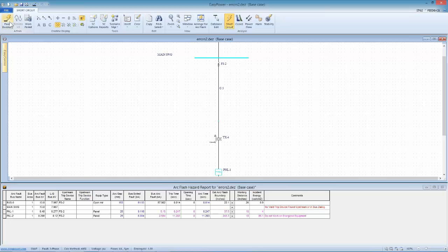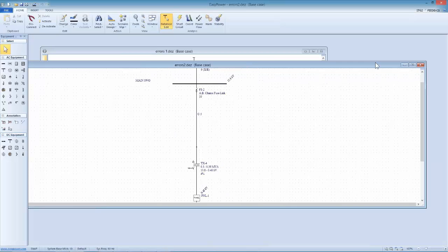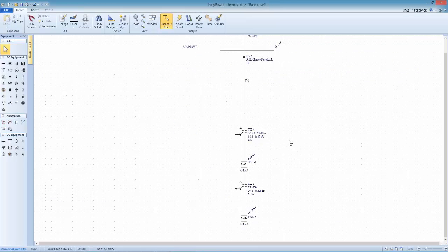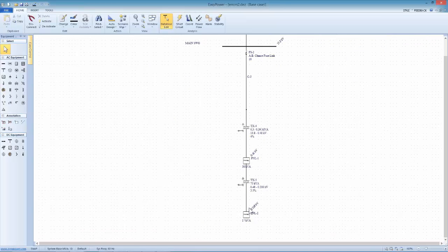So at that point, I realize I don't have any of my protective devices, other than the fuse, filled in. So I need to go back to the database editor and look at each of the elements. Now again, I'm still in my very simplistic mindset. I expect to see some protective devices in this panel, and I see some down here. So the question is, why aren't they being picked up by the system?